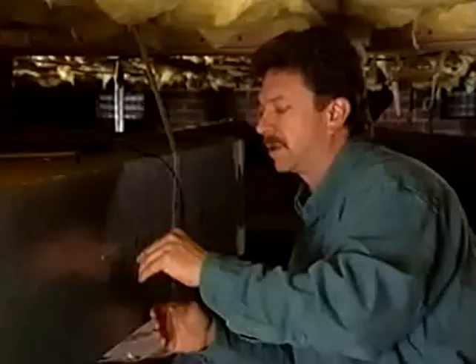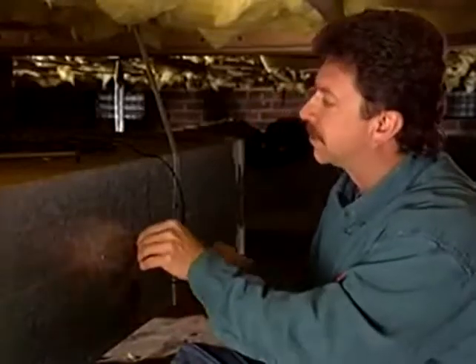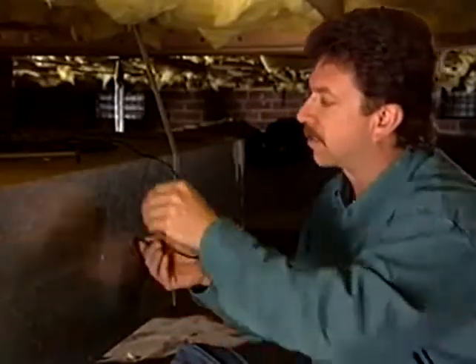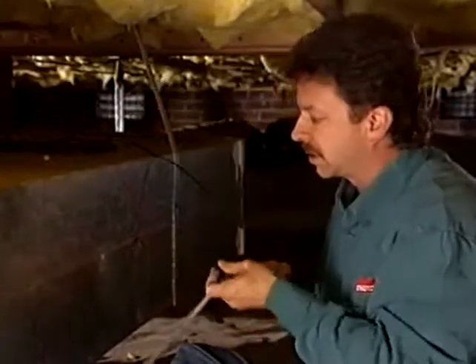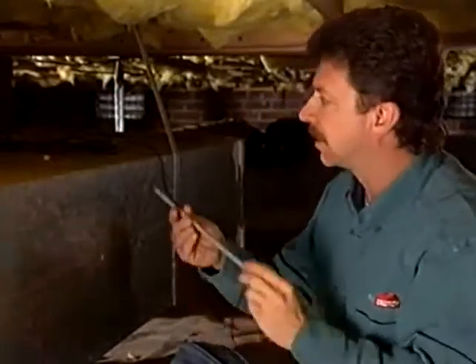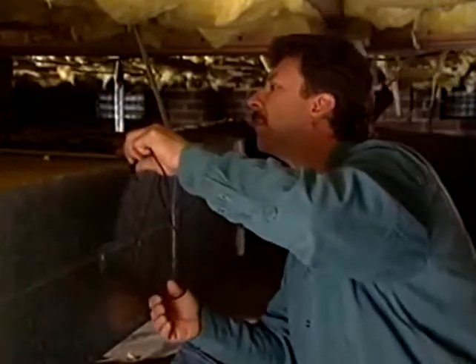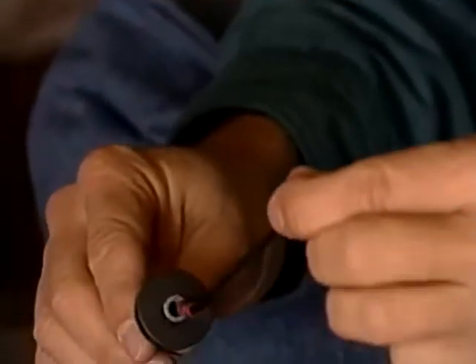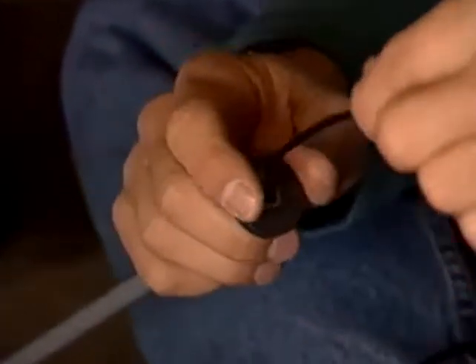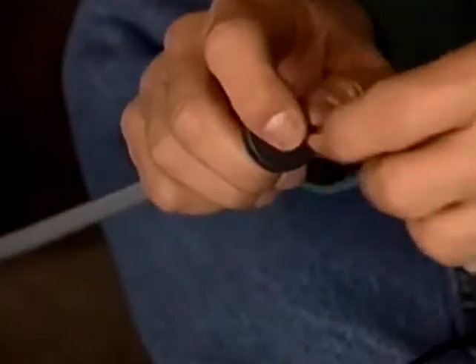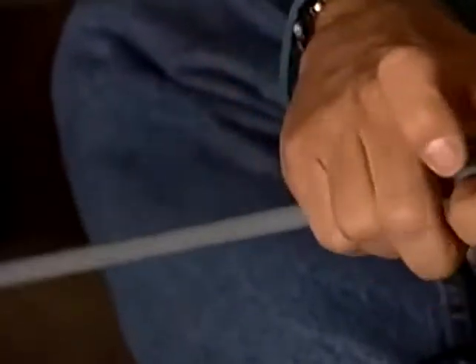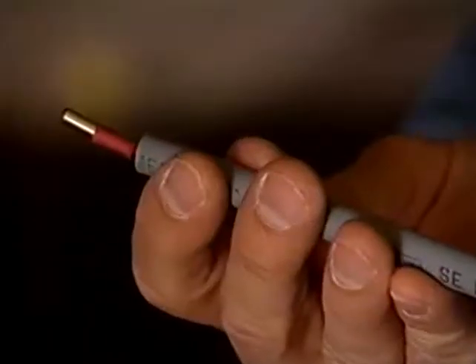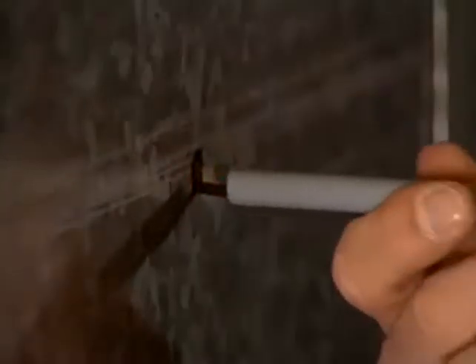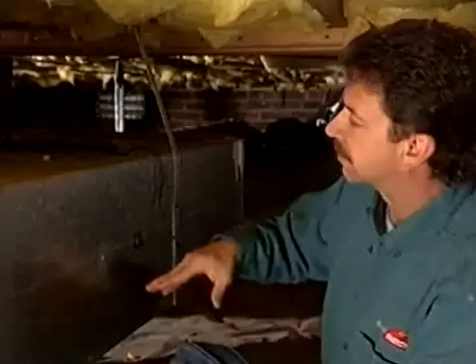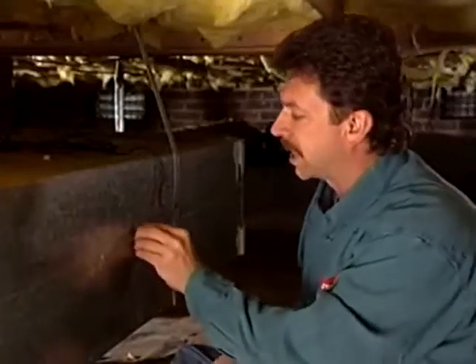Although putting it in the center this way, it's going to have a tendency to drag the bottom, and you could get some static pressure there that could give you some false readings. Normally what I'll do is take a piece of Quest pipe and cut it about the middle of the ductwork. Got a little toy magnet on it. We'll take the temperature probe and just barely push it out the back side. And that's going to stay pretty close to the middle. It's not going to drag the bottom. It should give you the most accurate reading.